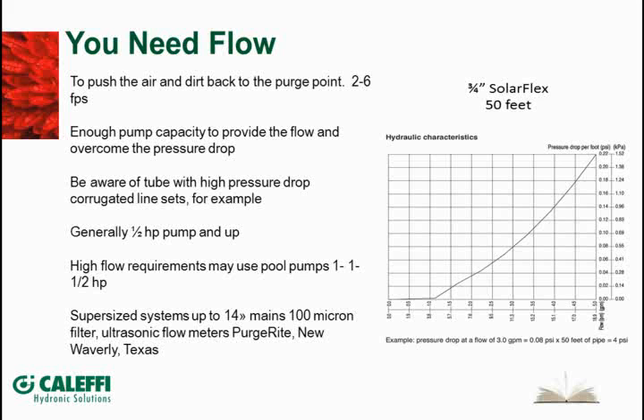Because if the velocity drops below 2 feet per second, the water moving through the pipes doesn't push the air in front of it and won't push it back to a point where you can eliminate it from the system, either at your purge valves or back at your air separator. And if you flow too fast, the water and air just mix. It's almost like a blender, and you'll see bubbled air and water coming back, and it's hard to separate the air out if you're going through it too quickly.